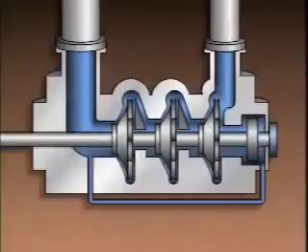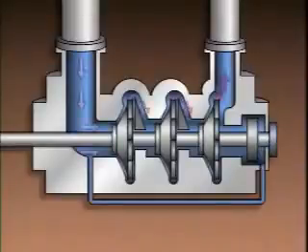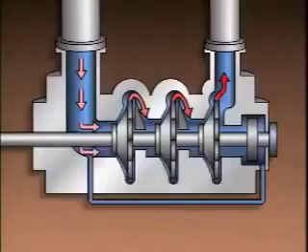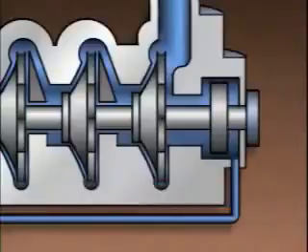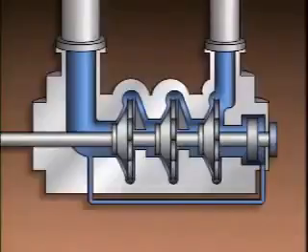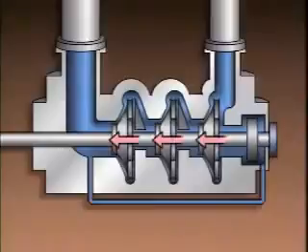Regardless of how the impellers on a centrifugal pump are arranged, or how many stages a pump has, the liquid's pressure increases as it passes through each stage. This creates a thrust across the impellers in each stage. This thrust, known as axial thrust, is caused by the difference in pressure between the suction eye and the volute, and it tries to push the pump shaft toward the suction eyes. In order for the pump to operate properly, the thrust must be offset. On some pumps, the thrust is offset by using a thrust bearing, or a device known as a balance piston or balance drum.